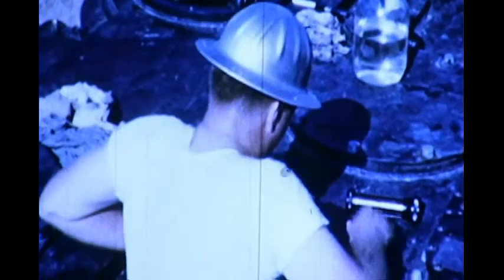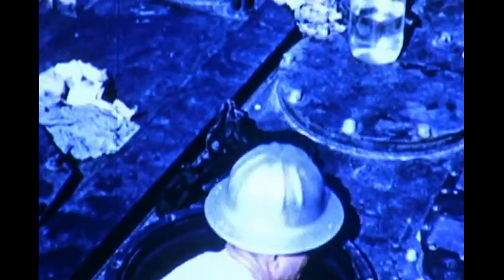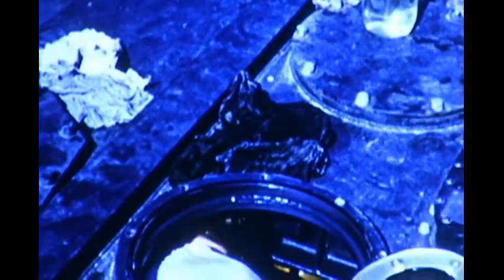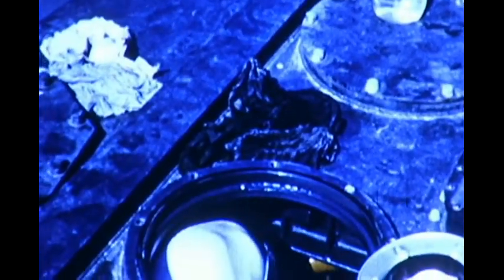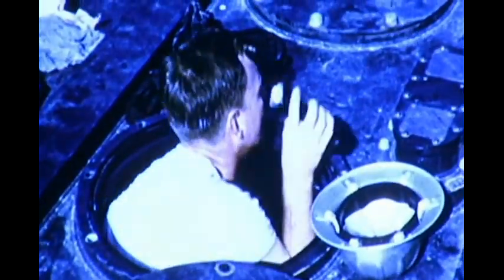Now, with the liquid at the top of the core, we are ready for an inspection of the interior. A General Electric field engineer using a flashlight makes a thorough check to see that internal parts have not moved or shaken loose during shipment. To prepare for the next step, the installation of bushings, the high voltage leads are brought out and the protective tape used for shipment is removed.